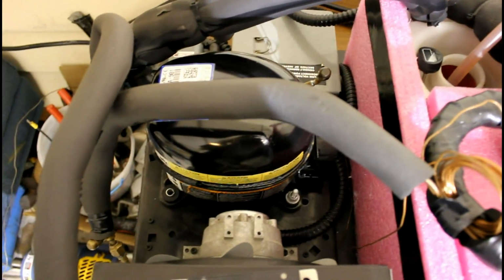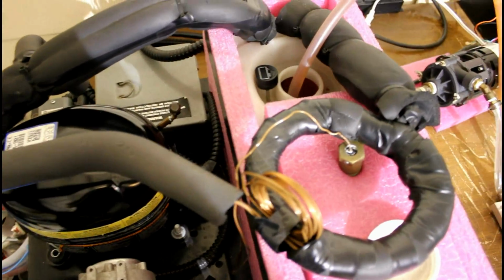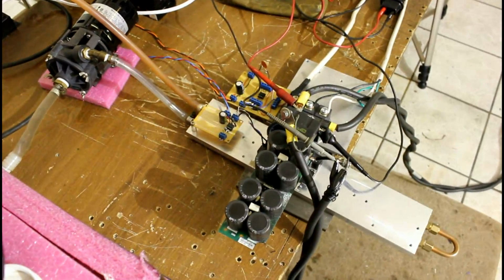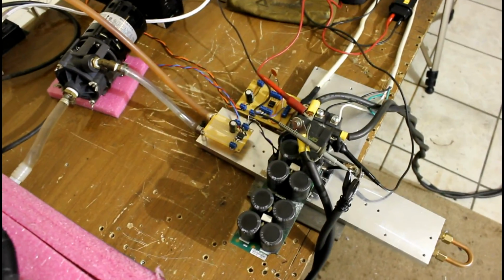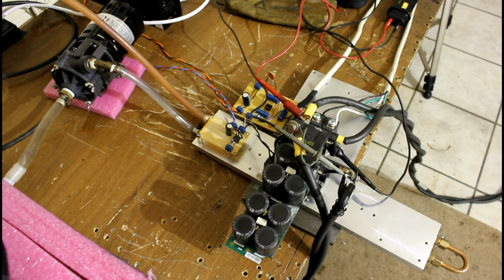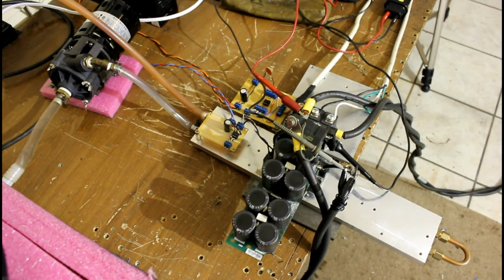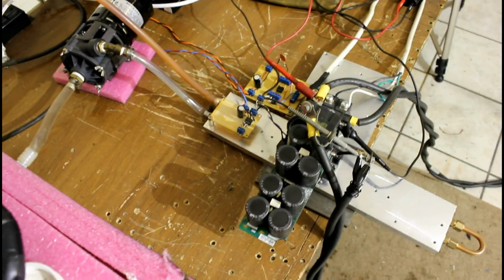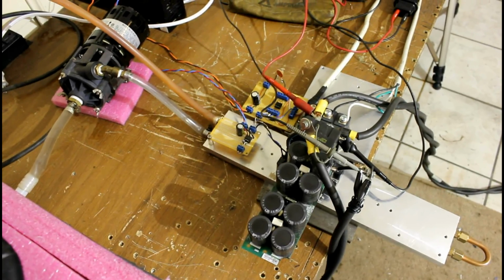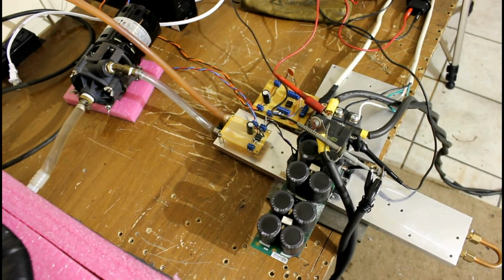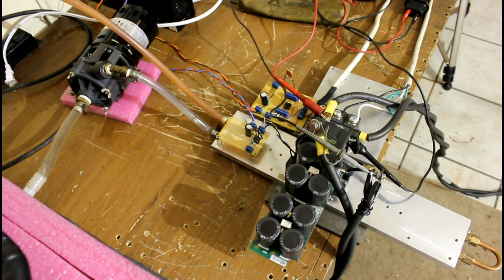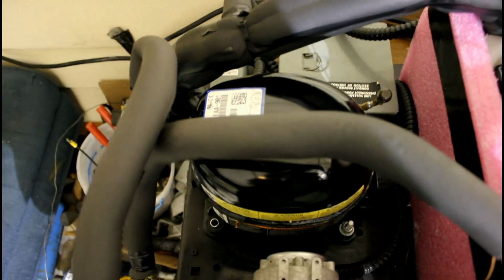This one is a chiller, so it cools liquid. We're going to run it through the heatsink of our IGBT test setup. I'm going to show you the IGBT running with a larger than recommended gate resistance value and a greater than recommended current value. In a minute we will see that.